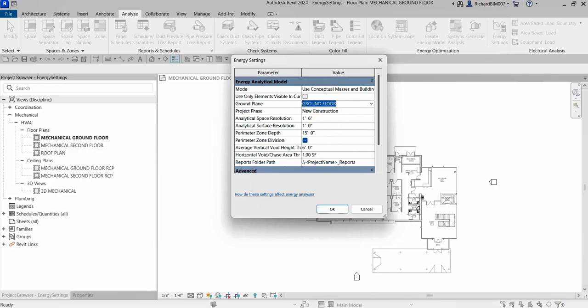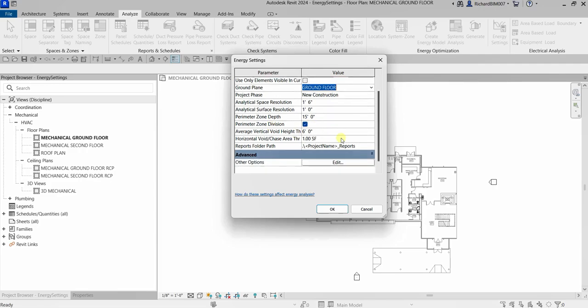You also have Perimeter Zone Depth — specify the distance to measure inward from the exterior walls to define the perimeter zone. This setting should always be used in conjunction with Perimeter Zone Division. There is also Average Vertical Void Height Threshold — this value is used to avoid the application of unwanted thermal loads and properties to analytical spaces like ceiling voids, closets, and small storage spaces.